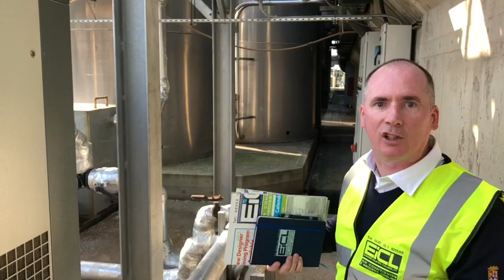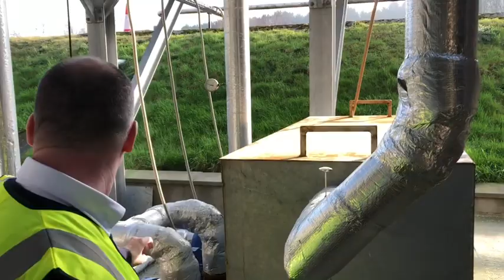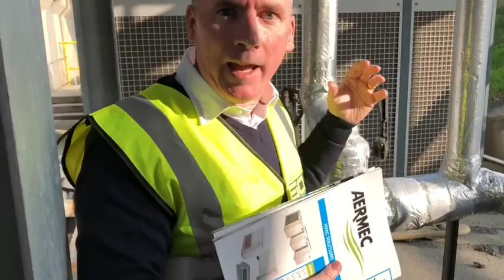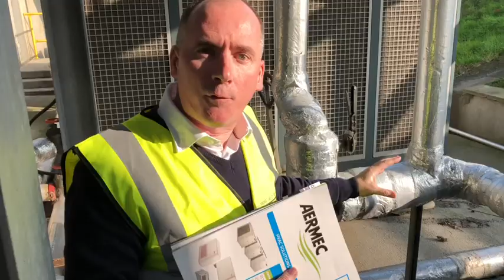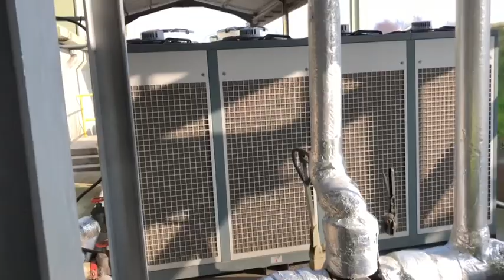Okay, so with this system design, we have the load, which is the warm water coming back from the factory. So just see the sun is behind me there, so if you just step over there a bit. Okay, so we can see the load is basically coming back here from the factory. That's the warm water. Comes down into a buffer tank. So we're into the warm side of the tank here. We then come out of the tank through a three-way valve. And then this valve, dependent on the ambient temperature and the chill water set point, will determine if the ambient is low enough and we can avail of free cooling. The water is diverted up, as you can see, through this big dry cooler we have here.